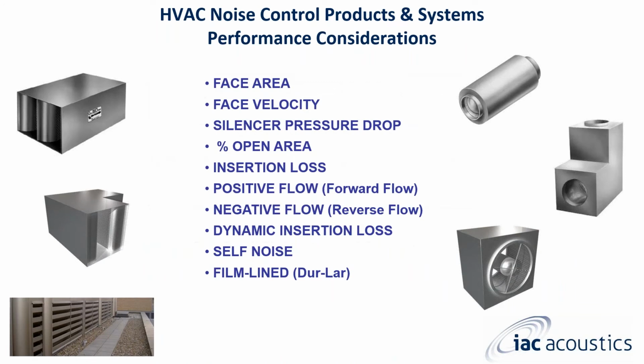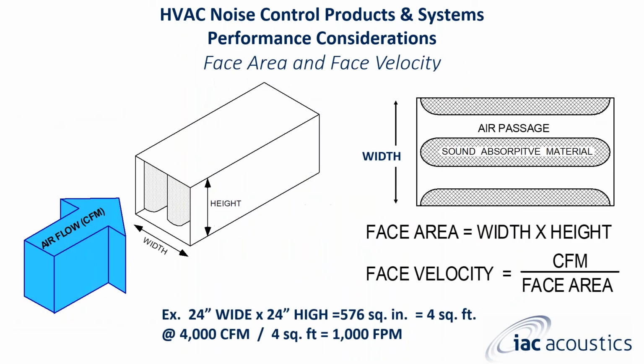What we're going to go over today are some performance considerations. You might already know these, but again, it'll give you a nice refresher for some basics. First, we'll start off with face area and face velocity. Face area is width times height. Take that in square inches and convert that to square feet. Face velocity then is take the CFM of what the piece of equipment is producing, say at 4,000 CFM, divide that by your face area, 4 square feet. You now have 1,000 feet per minute.